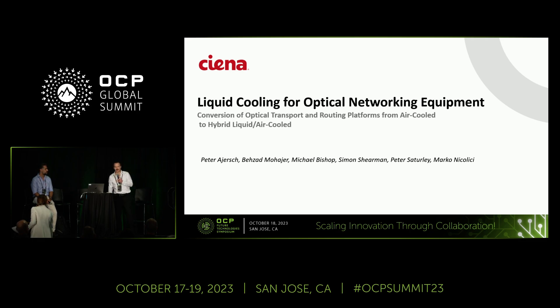My name is Peter Ajersch. I'm a thermal engineer with Ciena, as is my colleague Behzad Mohajer. Ciena is a producer of optical networking gear. Some things that we're very good at are long-haul coherent transceivers, packet and OTN switching, and data center interconnect. What I'd like to talk to you today about is the work that my very talented colleagues and I have done to develop a migration path from an all-air cooled system to a liquid cooled system without redesigning the equipment from the ground up. When I talk about liquid cooling, what I mean in this context is hybrid liquid-air cooling. We keep the fans on, running at low speed and quietly to cool the multitude of lower power devices throughout the system.